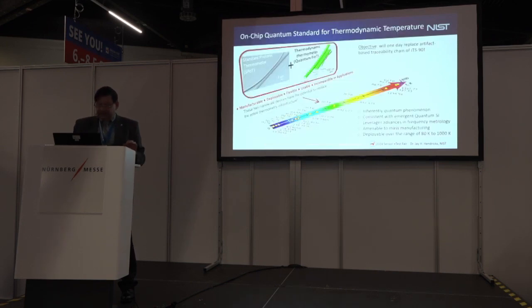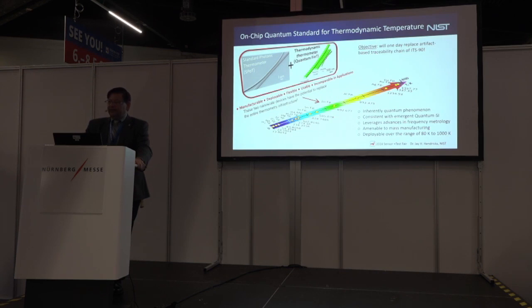The advantage of the photonic thermometer is that it is way more stable than the traditional SPRT in terms of what it can do. The classic SPRT, or standard platinum resistance thermometer, if you drop it or tap it or anything like that, the grain boundaries can change inside the platinum wire, changing the resistance and therefore changing its calibration. What we've seen with the silicon photonics thermometer is that it doesn't have any of those problems.